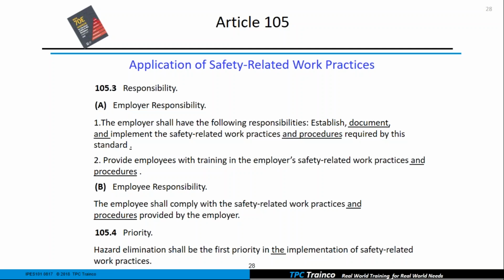The employee responsibility, a little bit there. Pretty much every place that we look at, we'll see that the only thing the employee has to do is follow the rules. So whether it's OSHA or NFPA really doesn't matter. The employee has to comply with all the work practices and procedures that the employer has provided to them. But even though the employee shall comply, it is still up to the employer to ensure that they are complying. So inside your electrical safety program, you should have something for consequences. We just can't let these technicians out there working with no PPE or whatever. They have to follow what we have in writing.